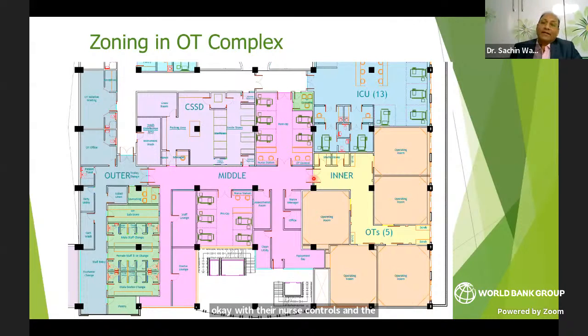After this you have one more barrier, the final barrier into the inner zone, where you have the sterile stores, the operating rooms, and the scrub stations. As we discussed with air pressure, this is where you have the maximum pressure, a little less in the inner zone, and even less in the middle zone. So air will always pass from the operating room to outside and from there to the middle zone, and it will never cross from the opposite side.